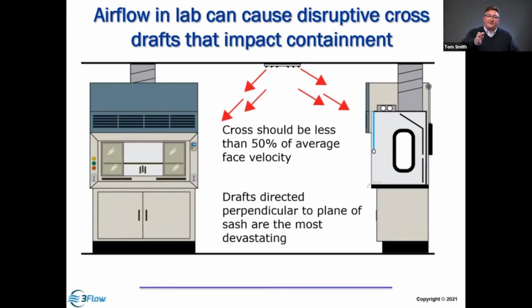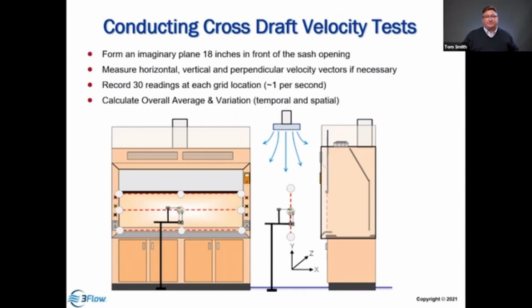If you put your hand in front of the hood, you can barely perceive 100 feet per minute. If you can feel the air blowing on you, it's too high. It's going to be much higher than 100 feet per minute. It's also important to note the direction of its impact on the opening, whether it's blowing vertically past the hood, horizontally past it, or directly at the opening. So we look at horizontal, vertical and perpendicular drafts, and those drafts are important for us to measure. So we can arrange our probe.